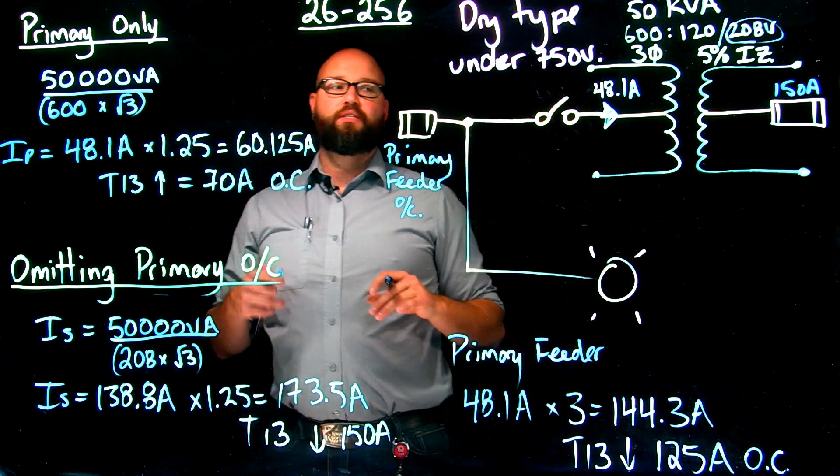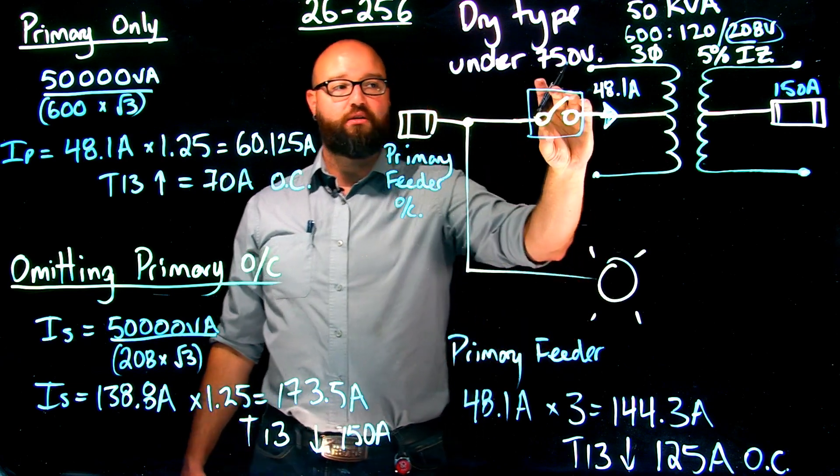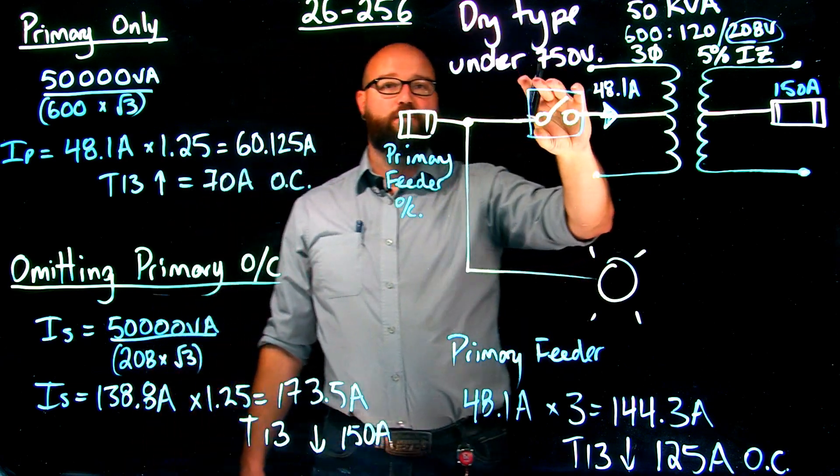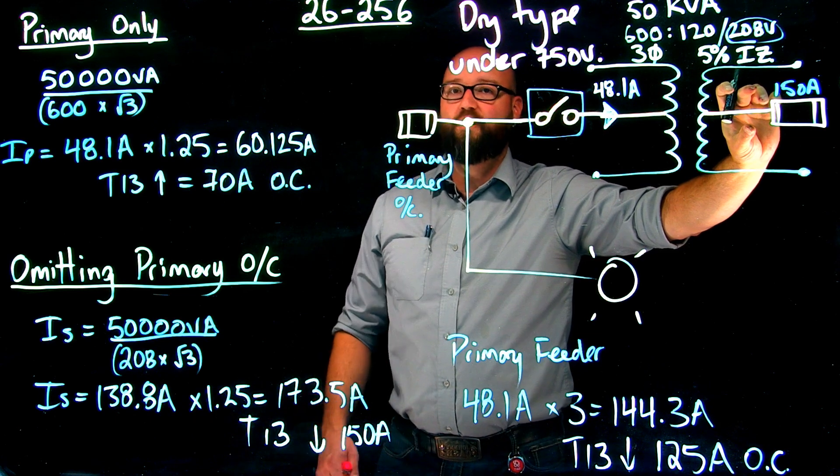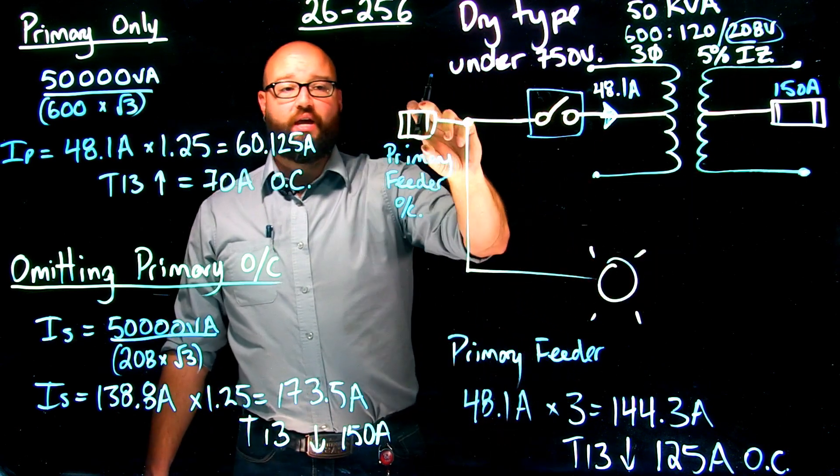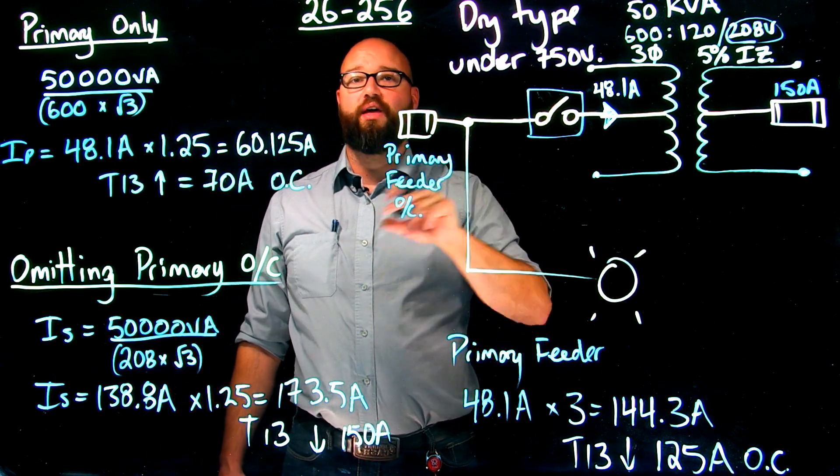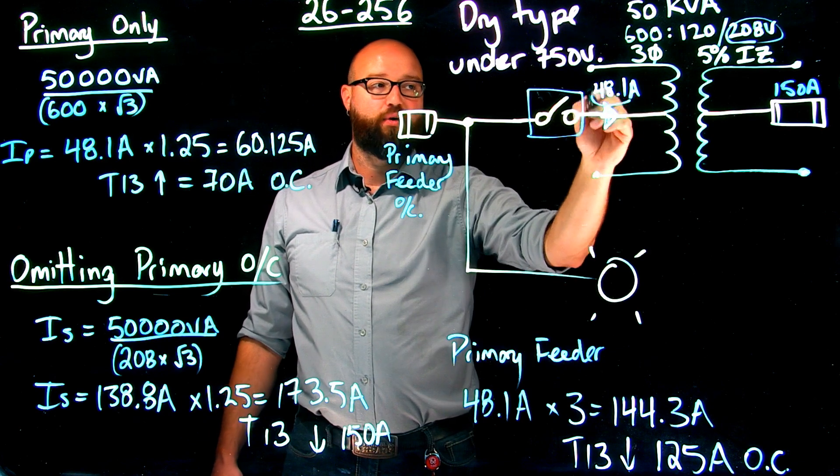So to recap on this example, if I want to omit primary protection, I am going to need to have a secondary overcurrent not more than 125% of rated secondary current, and a primary feeder overcurrent rated or set up not more than 300% of rated primary current.